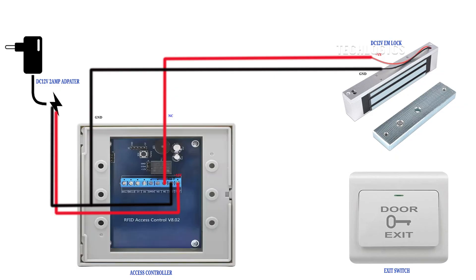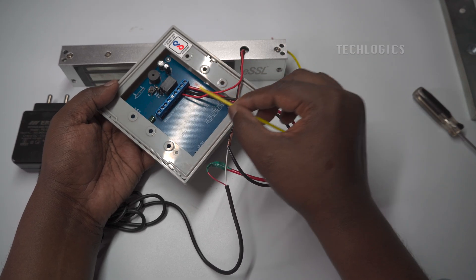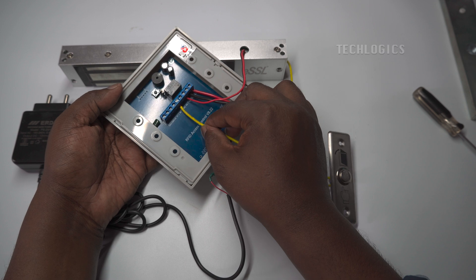Finally, connect the exit switch. This is a push-type exit switch with two terminals. Connect one terminal to the access controller's open terminal and the other terminal of the exit switch to the DC power supply's GND or negative supply wire.